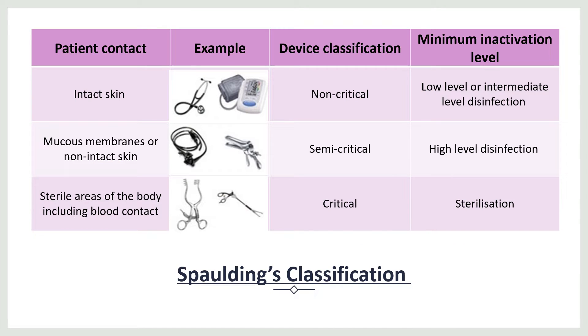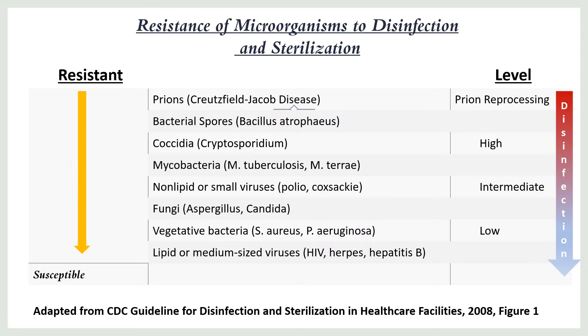Non-critical instruments are those in contact with intact skin. Semi-critical instruments are in contact with non-intact skin and mucous membranes, while critical instruments are those which enter into sterile areas of the body. An example of a non-critical instrument is a sphygmomanometer; semi-critical examples include laryngoscope blades; and critical examples include surgical instruments. Critical instruments require sterilization, semi-critical require high-level disinfection, while non-critical require low to intermediate level disinfection.